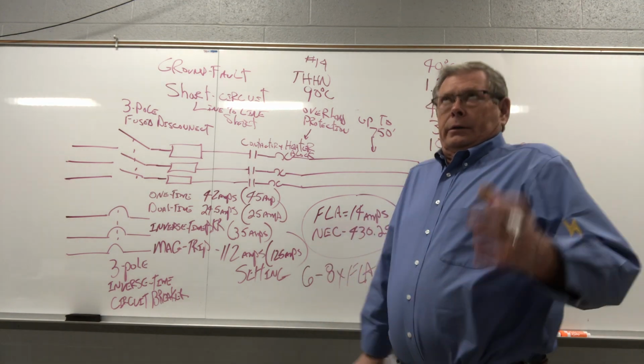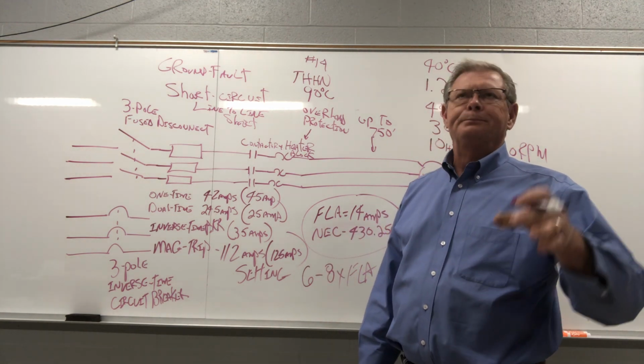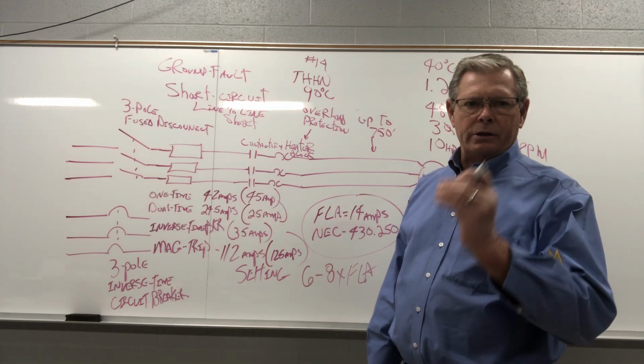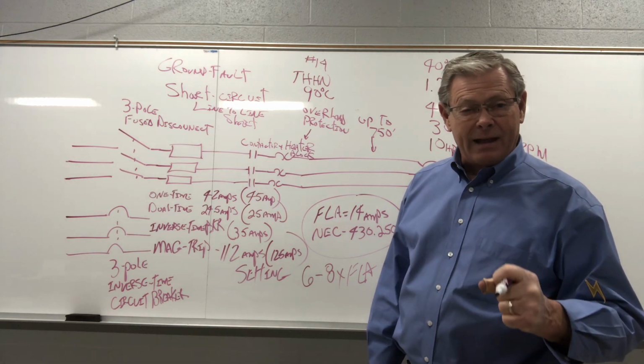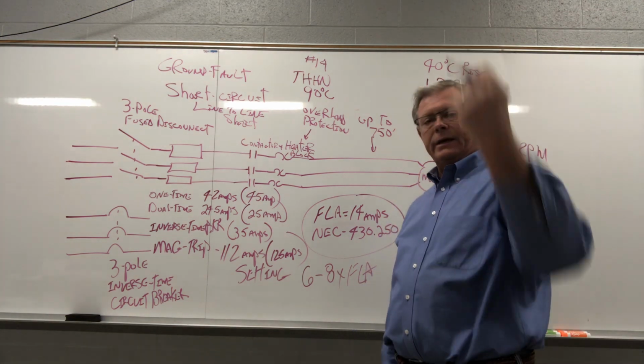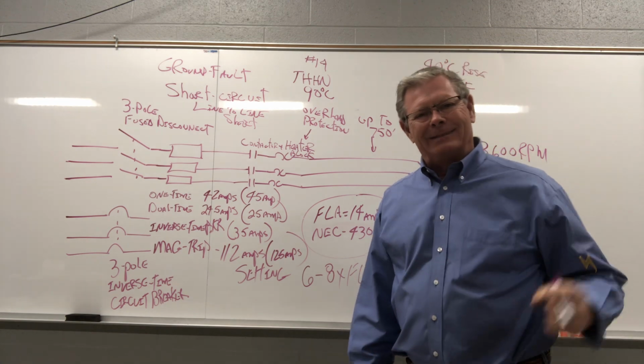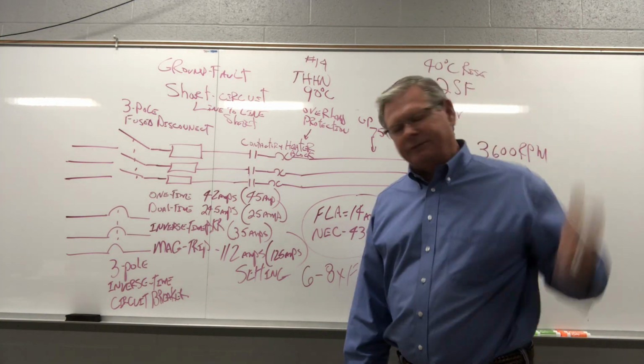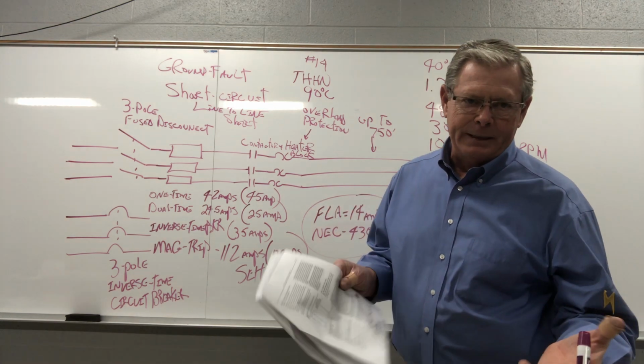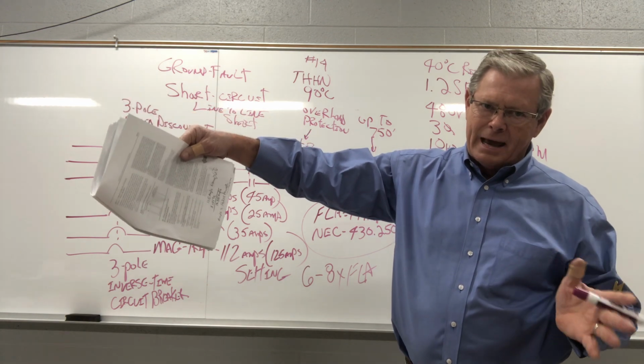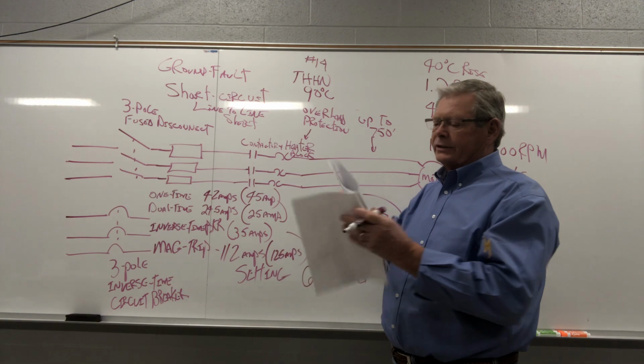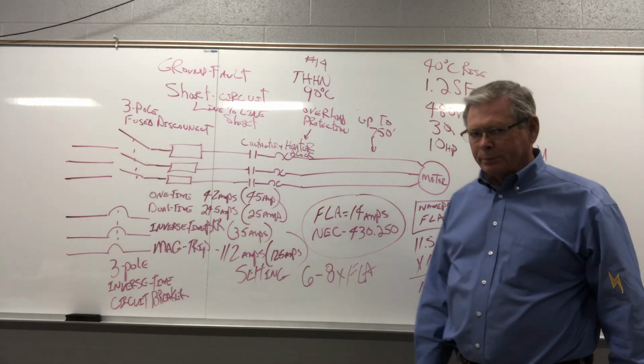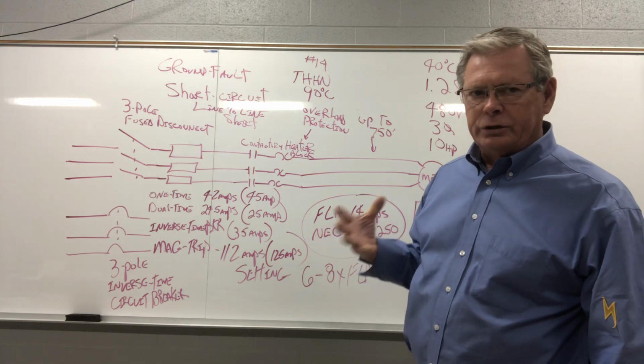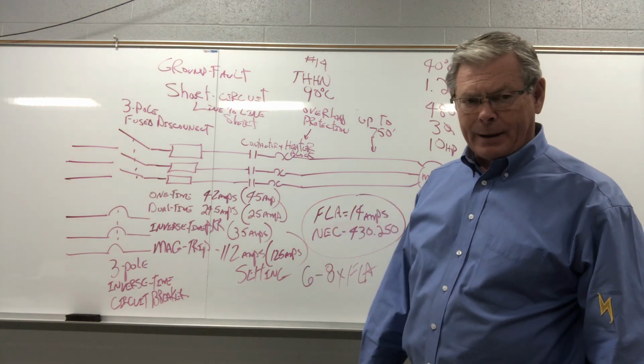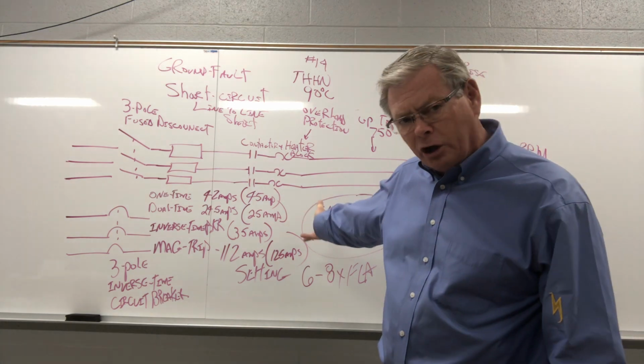Now, there's a difference. Remember us talking about starting current? It depends whether you have a high inertia or a low inertia load. A high inertia load like a flywheel. Low inertia load, you start a motor, boom, and it's running. A high inertia load, it's the flywheel. You hit start and it's turning faster and faster and faster and faster. Then it gets up to speed. So the amount of time that your starting current lasts matters with the load. So let's say that you size it with 125% on this particular motor and you're getting nuisance tripping. You take an amp clamp out there, you're not pulling too much current, you're just staying in starting current too long.